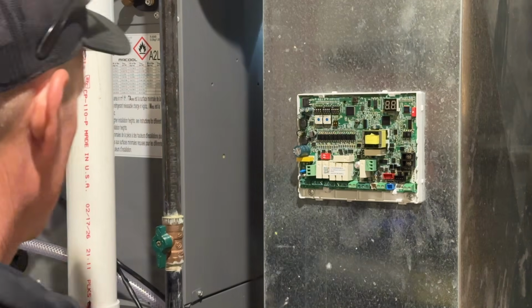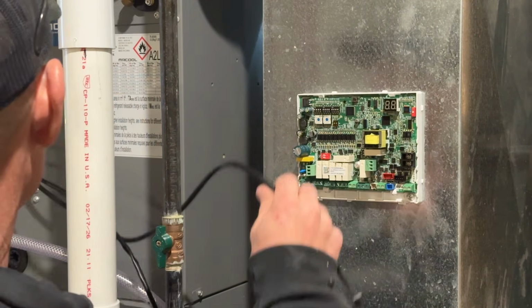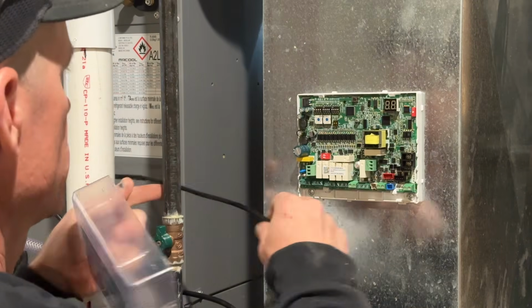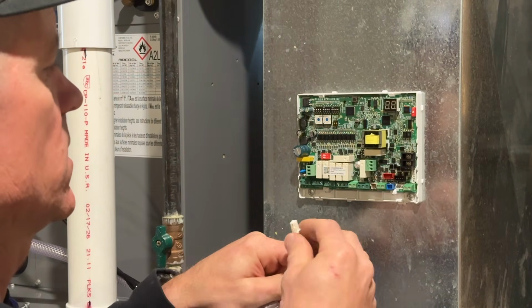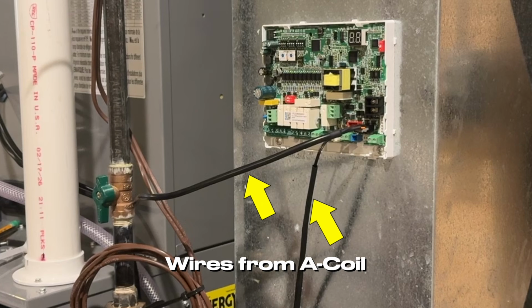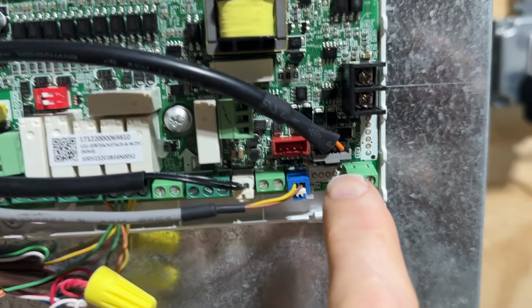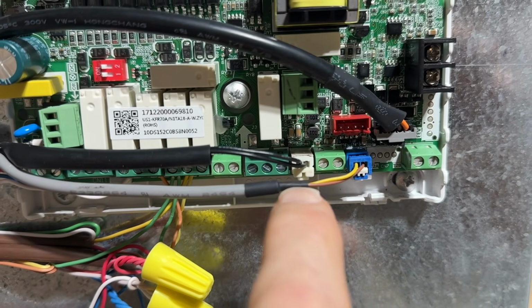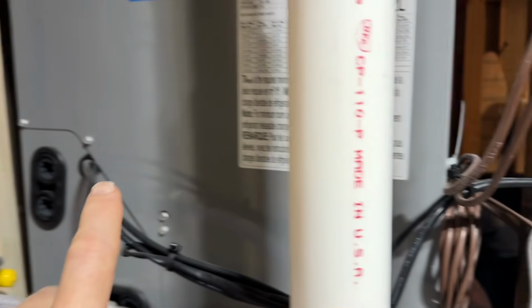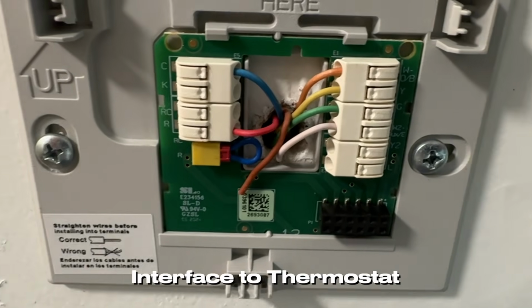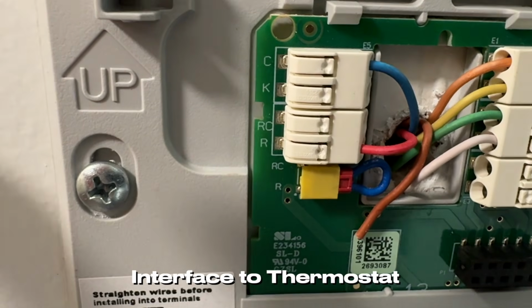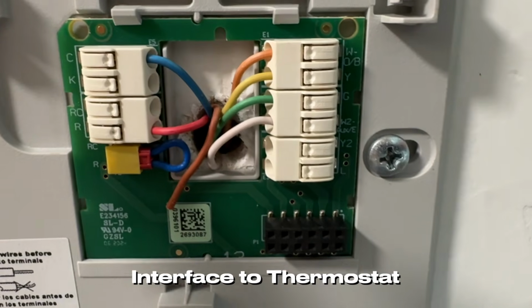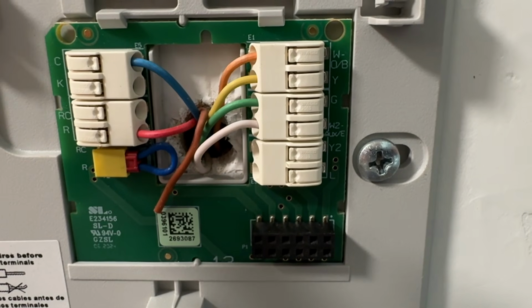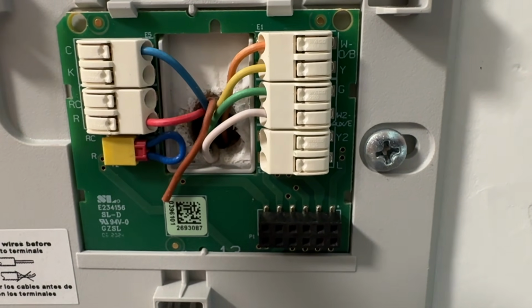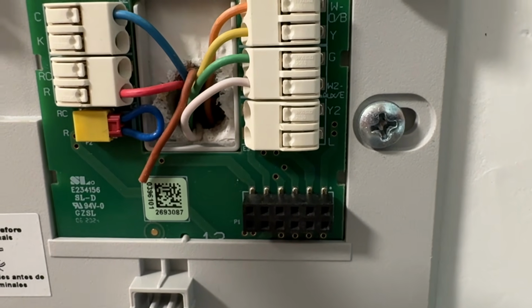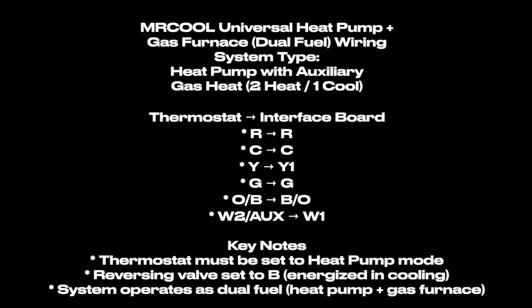All right, so these are the wires from the A-coil that I gotta plug into this, and they only plug in one way. That wire there and that wire there are from the A-coil. Okay, so this is the wiring to the thermostat. You'll see we have C and R hooked up. On the other side, we have W and OB, and when you program your thermostat, it will select the proper one. Then we have Y, G, and W2.